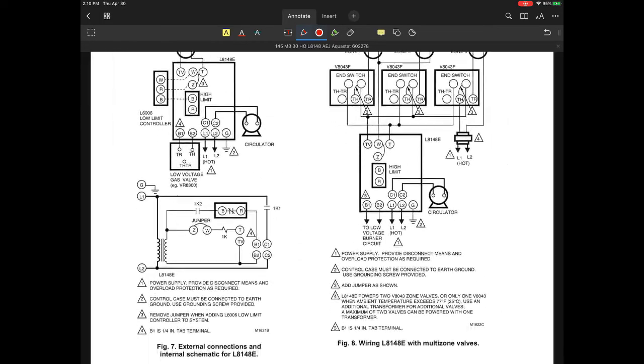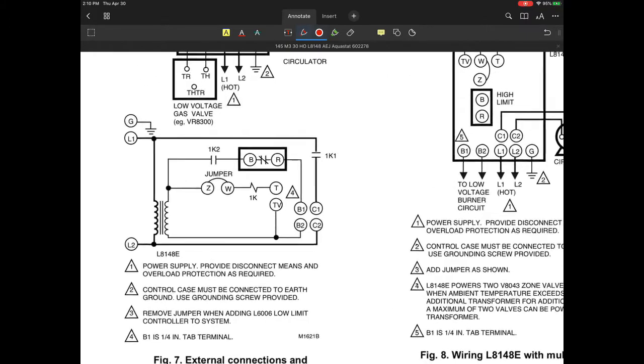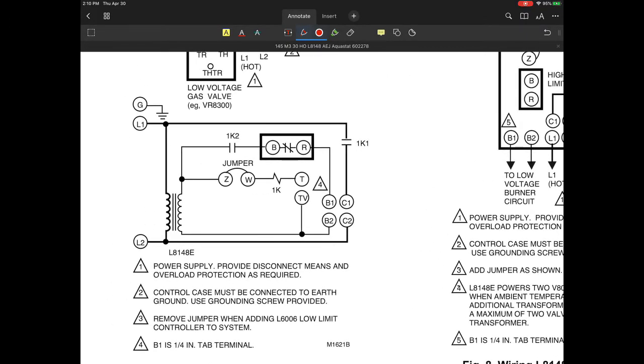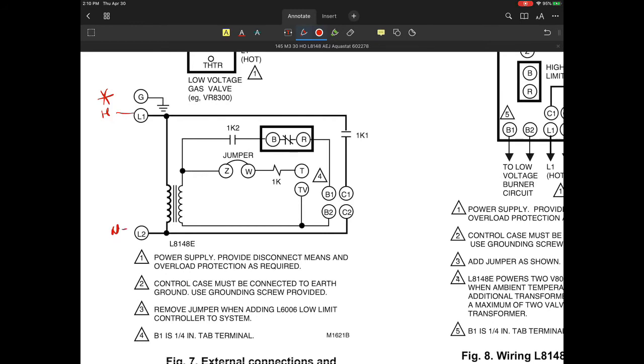So let's look at the specifics of how that is going to work. When we look at this diagram, let's look at the nitty-gritty details. The individual diagram of what's going on internally is really gold, so this is what you want to be looking at. My 120 hot and my neutral go into here; this is where I'm powering my transformer. But what you have in this one that you did not have in the other ones is the ability to power other things from this transformer, because now I have a spot where I can get a dedicated common from the 24 volt side, whereas before I never had that ability.